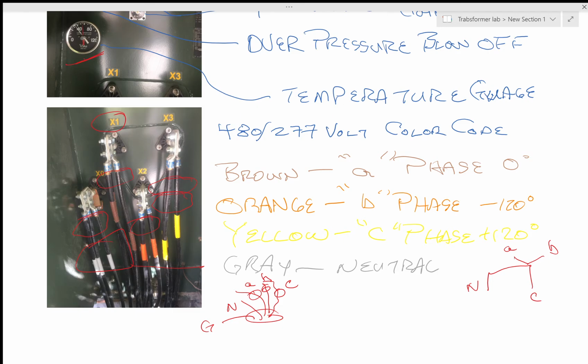Whereas if I have an A phase, a B phase, and a C phase, and I add the A phase current and the B phase current and the C phase current together, I get 0 current. Thus, the total magnetic field is eliminated in that conduit if I run an ABC phase in the conduit, instead of running all A phases in one conduit, all B phases in one conduit, and all C phases in one conduit. You never do it that way. You always run one A, one B, and one C.